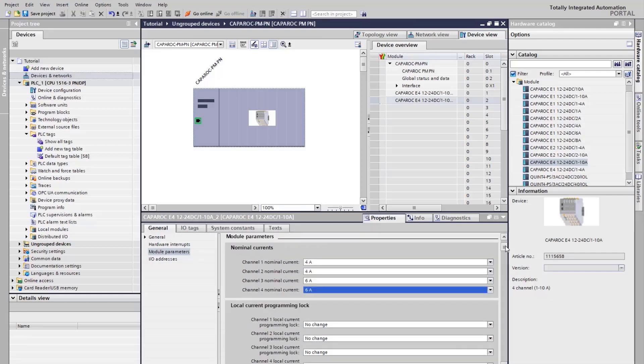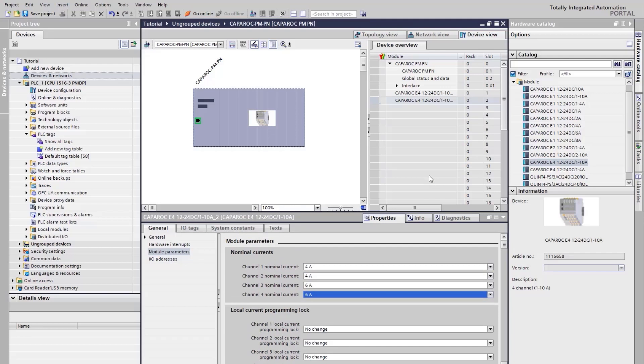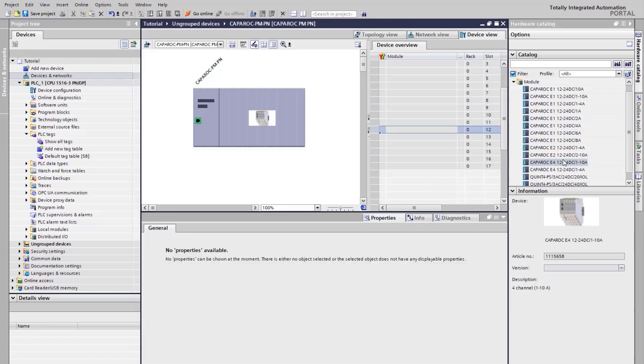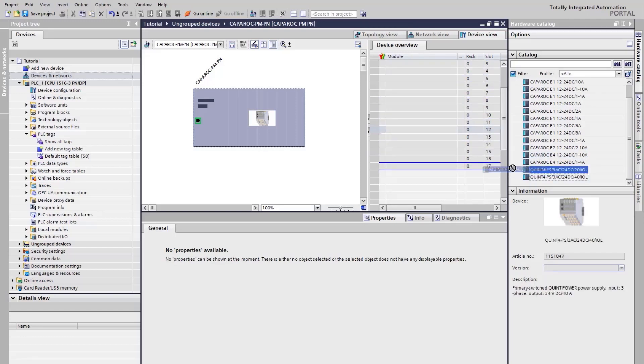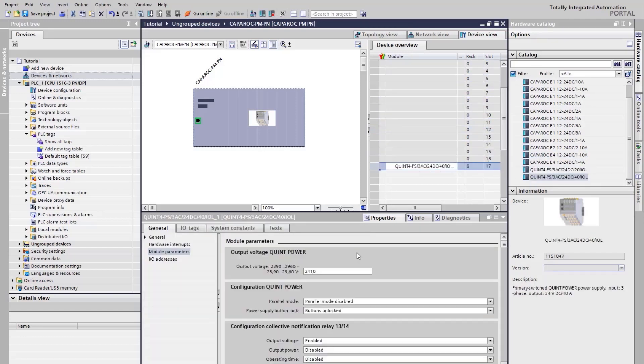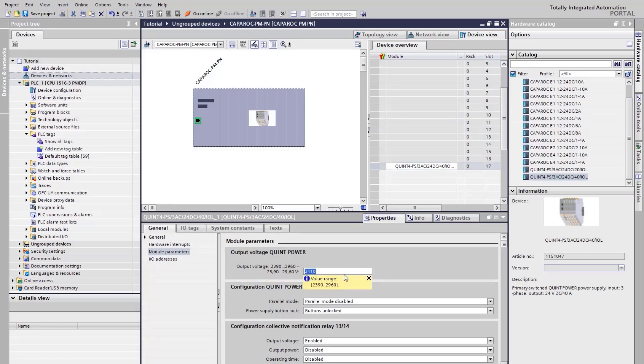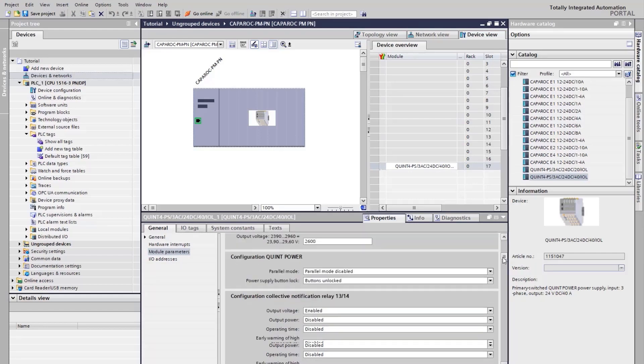After configuring your circuit breaker modules, select your corresponding power supply. Open the Hardware Catalog and add the QUINT Power power supply to the device overview. Choose the startup parameters for the power supply, like output voltage, the configuration of the relay contact, and more if needed. In this case, we change the output voltage of the power supply from 24.1 to 26 volts.